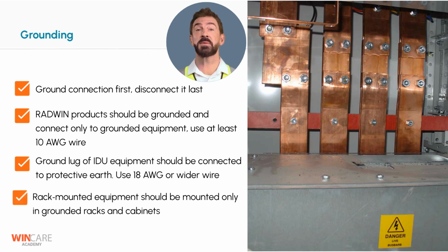Rack-mounted devices should be installed only in properly grounded racks and cabinets. Before disconnecting the ground lug, make sure all power and data cables are already unplugged. This prevents accidental surges and protects both the equipment and the installer.